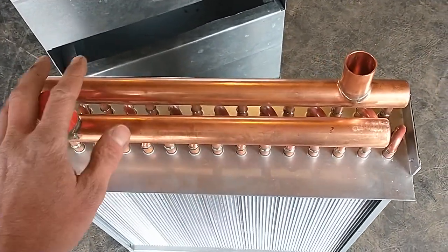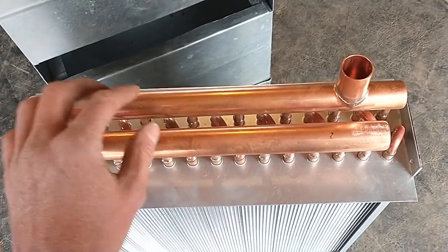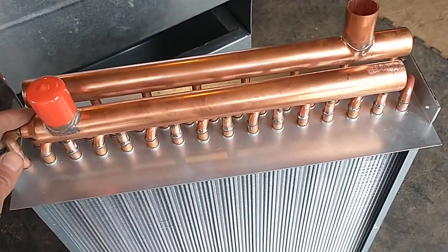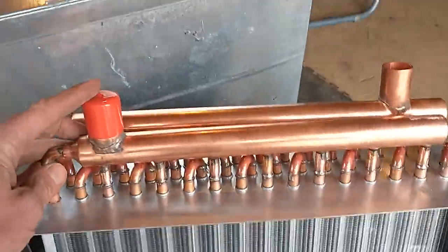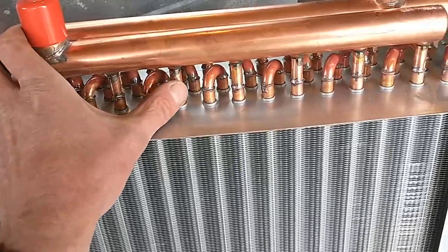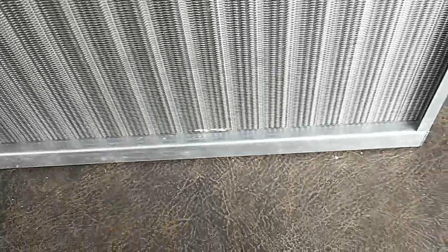It doesn't matter which manifold is which — I'll explain the direction of flow in a minute. You feed the hot water in and it goes through a whole row of copper tubes that are brazed together. It goes down through the coil through individual tubes with aluminum fins, roughly 12 per inch.